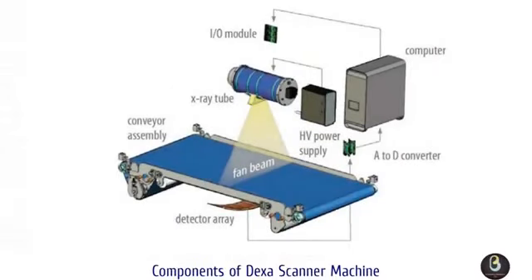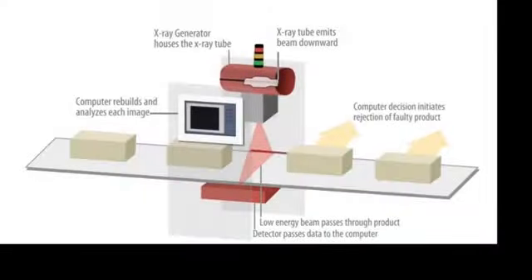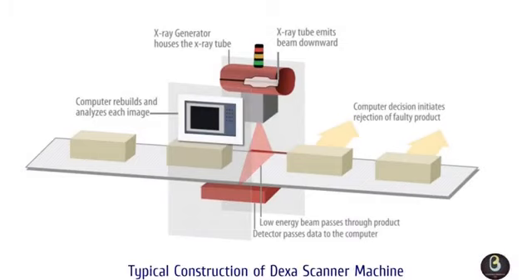The second component is the X-ray generator. The X-ray generator contains an X-ray tube which generates an X-ray beam. Modern X-ray tubes consist of a glass envelope, a filament cathode, a copper anode, and a tungsten target. The cathode, which is the source of the electrons, is a tungsten filament heated to incandescence by an electrical current. The electrons are accelerated to the target by applying a high voltage between the anode and the cathode. When the electrons hit the tungsten target mounted inside the copper anode, they decelerate rapidly, and this deceleration creates the X-ray emissions. Depending on the application, different X-ray tubes can be selected to optimize the sensitivity of detection and overall performance.